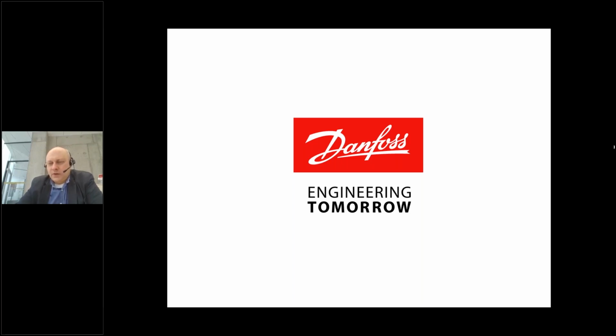They were based on practical discoveries from heating and cooling engineers from Danfoss. And if you browse the internet for a heat recovery unit datasheet, you will discover a table with a heating capacity chart and with cooling recovery data. And you would discover that mainly the scenario is very simple. As the Danes did, for shops smaller than 1,500 meters, they are offering solutions with one tank, and for shops with a larger capacity, they are offering two tanks.